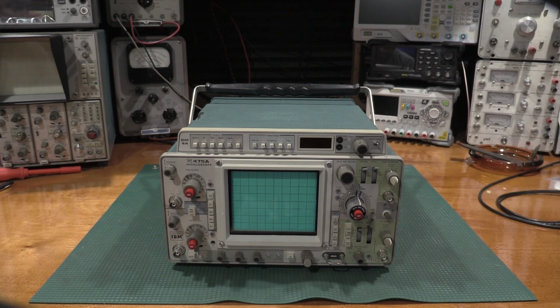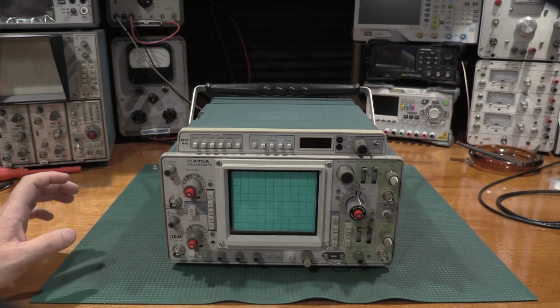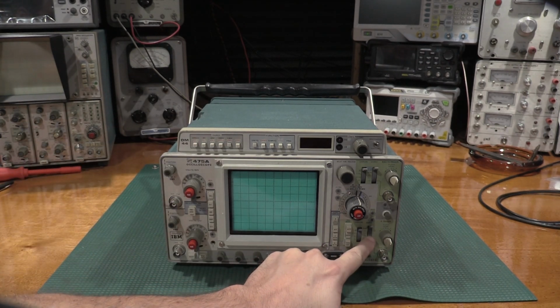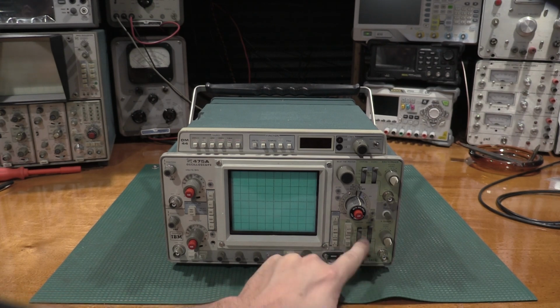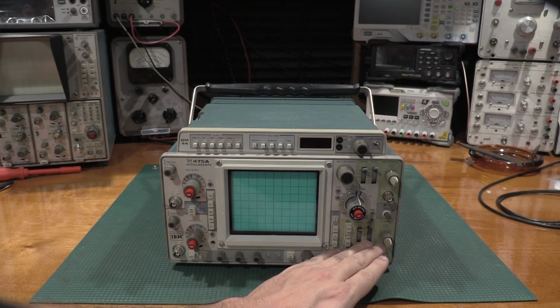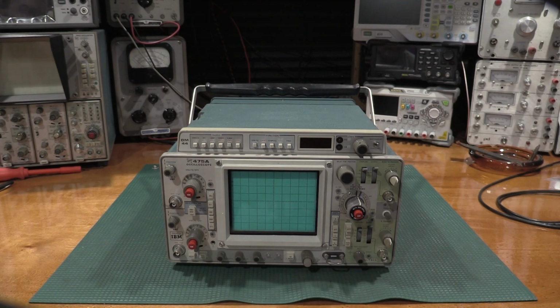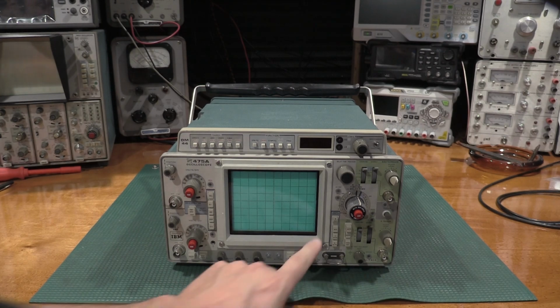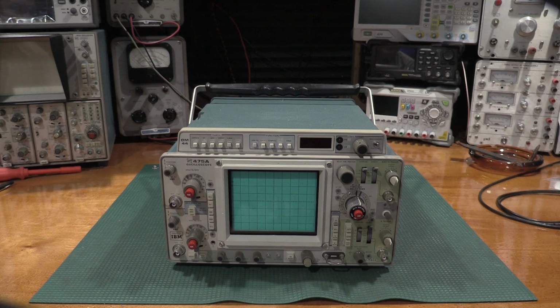So that's the first thing to take a look at: is the scope complete? Now, a couple of the things that I'm looking at before I even open it up is: are any of the knobs busted? Are these lever switches in here? If you remove the trigger board, these levers go with it. So if you see a scope that doesn't have these switches in there, pass on it. It's missing a board. Guaranteed it's missing a board. But from the front of this, everything looks good. Now, given that these are usually shipped, I've seen it where these buttons, this doesn't look too bad, but the scope won't work. If I apply power to this, assuming that everything was good, the button configuration on the front of this will not function.